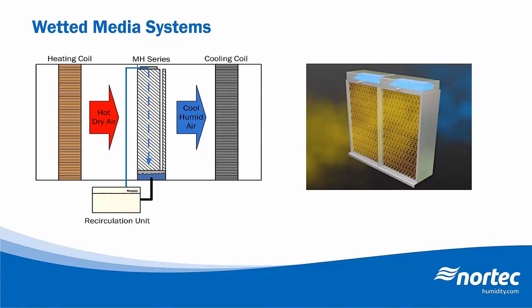Now, in order to help reduce overall water usage, the water that's not evaporated typically falls into a pan, which is then recirculated and pumped back to the top of the media. Now, one of the main benefits to using an evaporative media system is that it can operate on any type of water. So it can run on potable water or treated water, so RO or DI, unlike an atomizing system or an ultrasonic system that do require treated water.